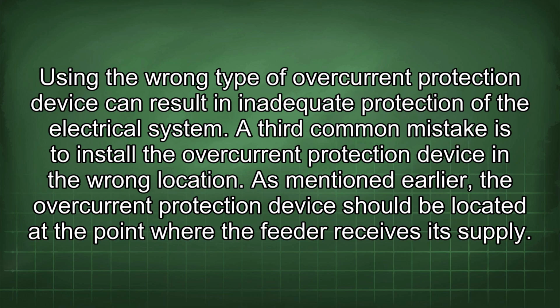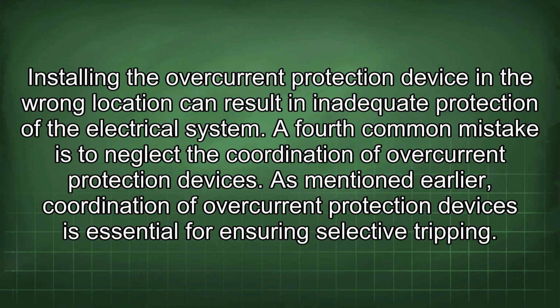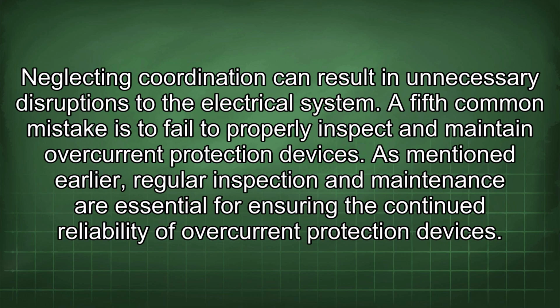A third common mistake is to install the overcurrent protection device in the wrong location. As mentioned earlier, the overcurrent protection device should be located at the point where the feeder receives its supply. Installing the overcurrent protection device in the wrong location can result in inadequate protection of the electrical system. A fourth common mistake is to neglect the coordination of overcurrent protection devices. As mentioned earlier, coordination of overcurrent protection devices is essential for ensuring selective tripping. Neglecting coordination can result in unnecessary disruptions to the electrical system.